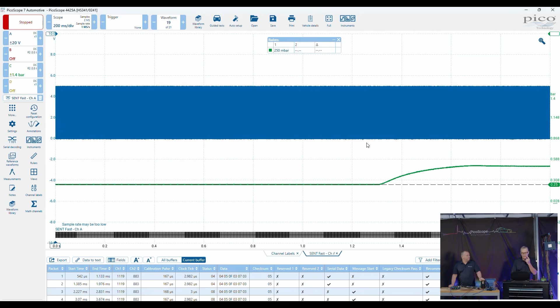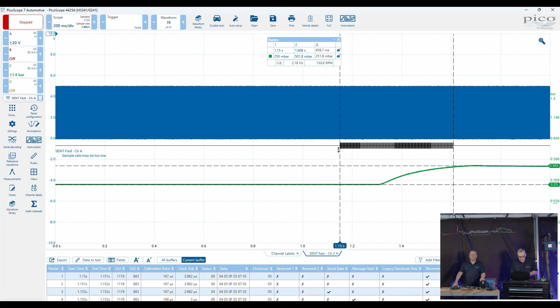If we amend the decoder and ask it to decode between the time rulers, click finish. Now nothing's going to happen because we don't have time rulers in place, but I want to focus on the area where we went from one state to another, where there was change. You can see in the graph view, the adornment, that we are only decoding between the time rulers, so we've minimized the data we have to look at. If we start slowly here, channel 1 was 119. Then as we scroll down, you'll see we change from 119. So now our raw data on channel 1 is changing in relation to the pressure that's been applied to test port 1.